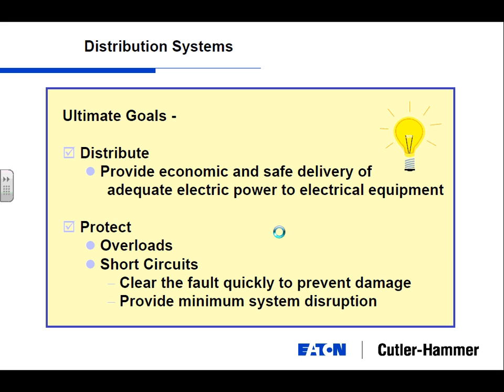If I've got a 100 amp circuit and I go in there and plug a 120 amp load in there, nothing's going to happen immediately, but over a time period, whether that's 15 minutes, 30 minutes, 30 hours, depending on the equipment you have protecting it, that will trip that circuit offline and, for lack of a better word, save the circuit. Your wire's not going to burn up. Your equipment's not going to burn up. The wire itself feeding the load is basically a giant fuse. That's all a wire is.